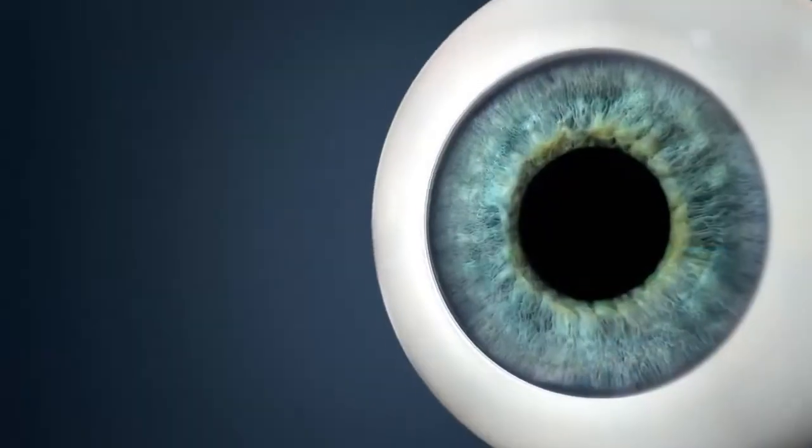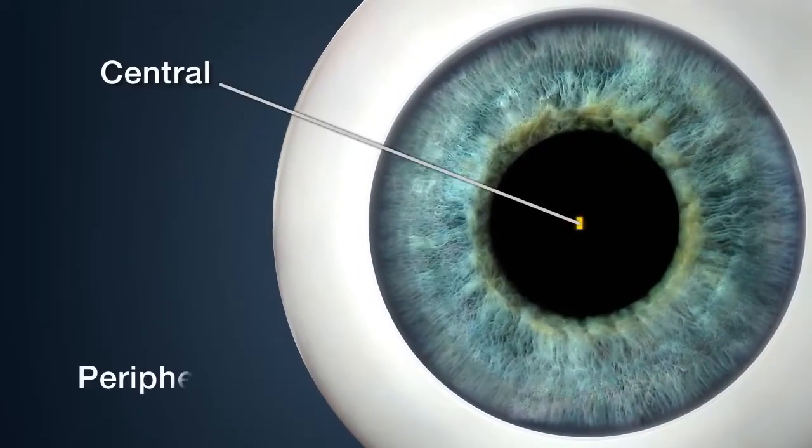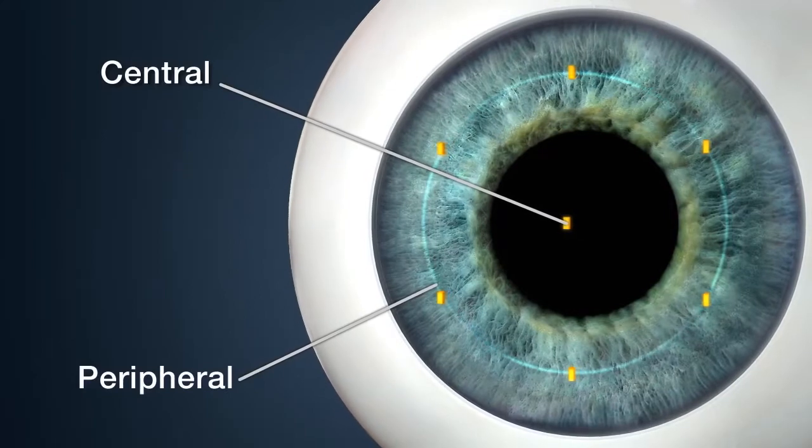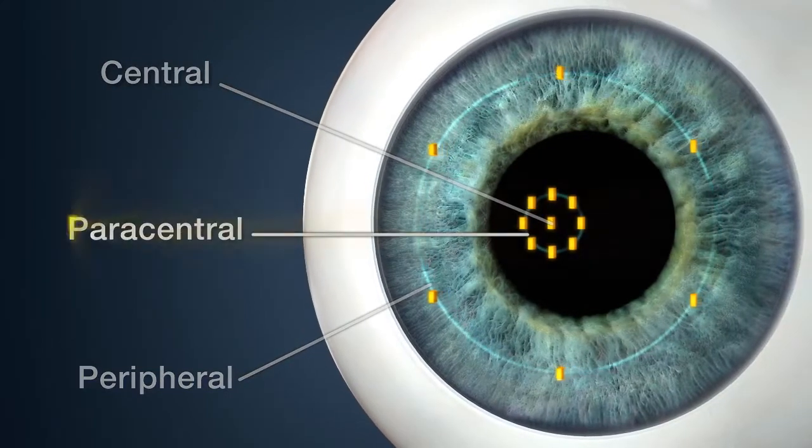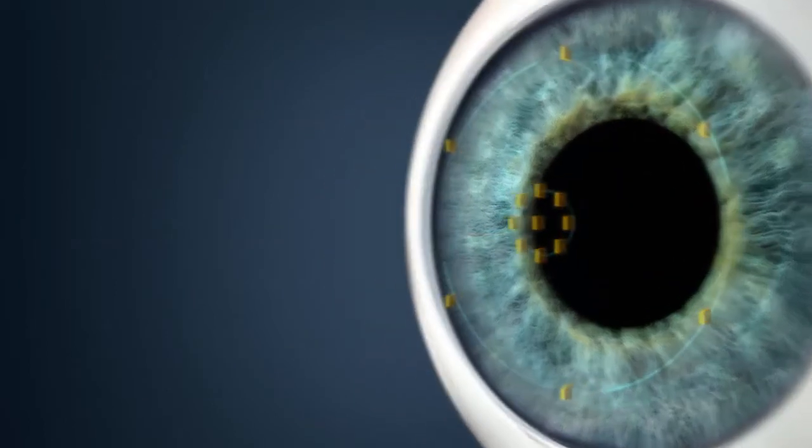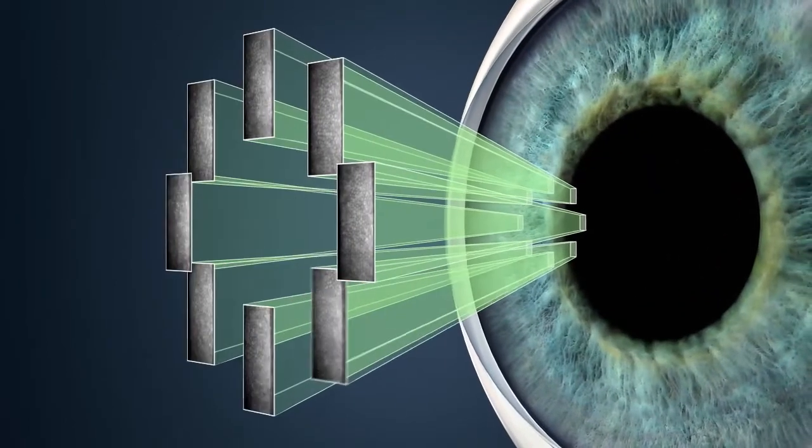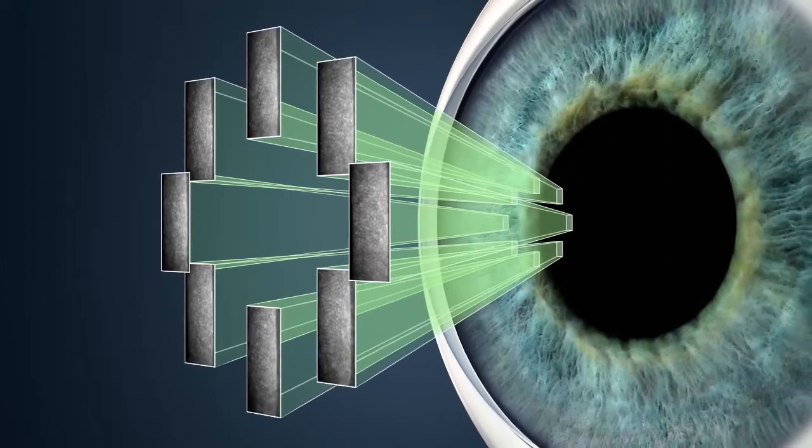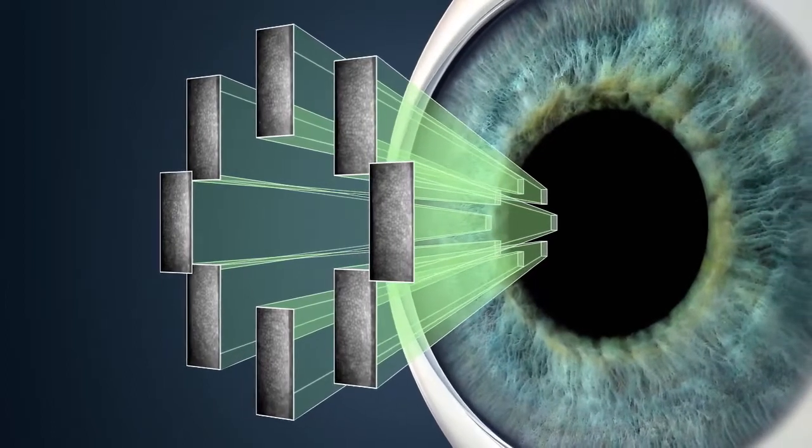While other specular microscopes may have central and peripheral imaging, the CEM530 incorporates paracentral imaging. Paracentral images are captured from 8 points at a 5-degree visual angle for enhanced assessment around the central portion of the cornea.